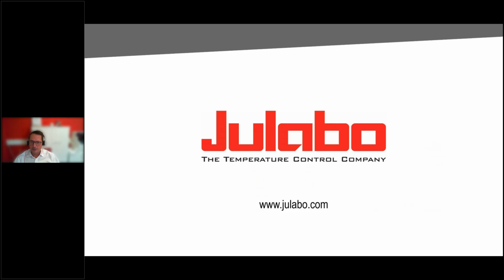Can you recommend something, Gary? Yes, I can. Lots of interesting questions there. And what I would do is I would come back in a series of questions. The first thing I would say is with Peltiers, if you're going below, and it depends on the environment, but if you're going below about minus 10, you're going to struggle. Especially when you have a high environmental temperature, a Peltier is going to struggle. Now, Julabo does do Peltiers, but if you have an environmental temperature of above 25 and a demand below minus 10, I would say that a Peltier is not for you.